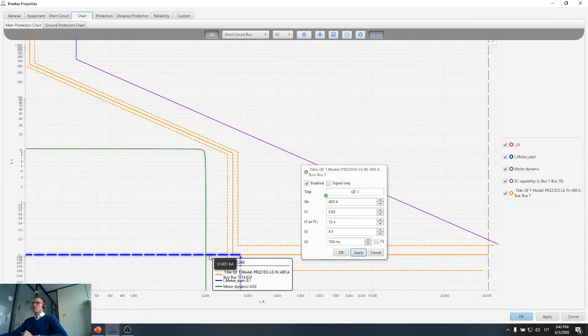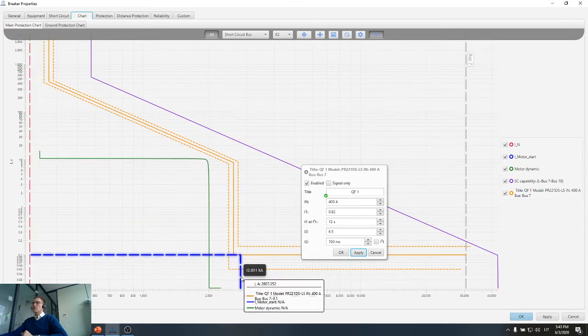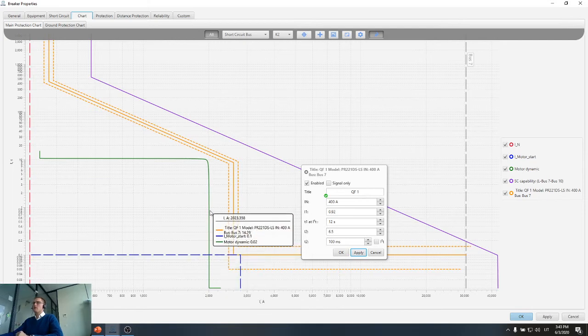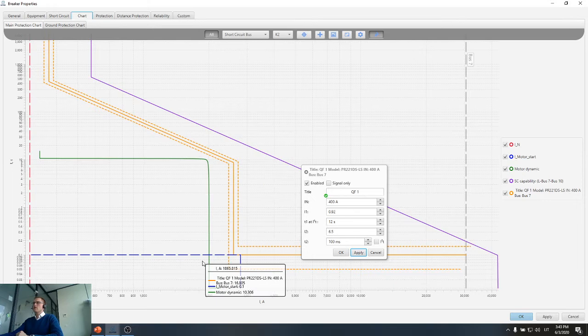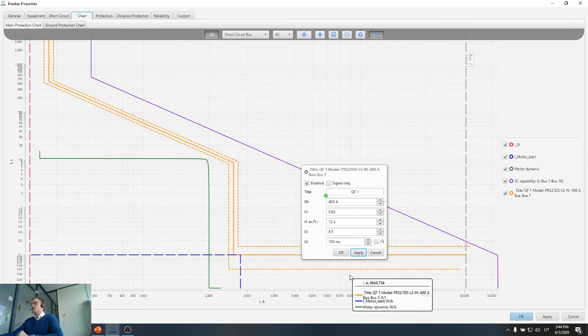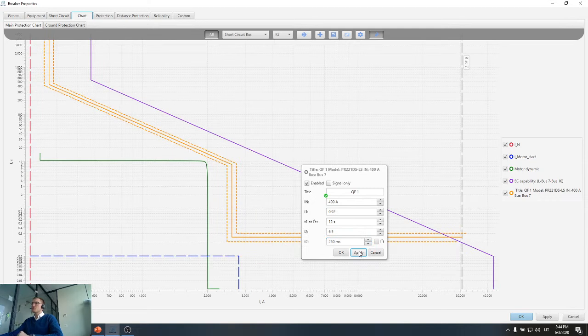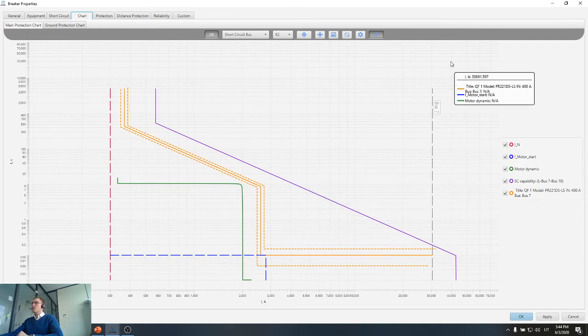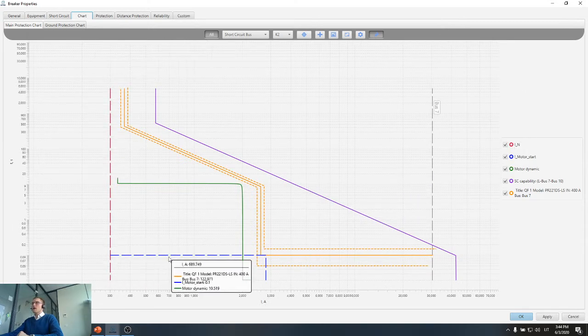Because I see that the recommended calculated motor starting current by the simple starting method is a little bit bigger, I would like to put some safety margin from the dynamic motor starting current, to avoid any tripping during motor starting. Also I can set the short time stage operation time, and here it's 100 milliseconds, which is basically the minimum that is allowed to set for this protection device. I can only increase it, but increasing this time would not be necessary, so I will leave 100 milliseconds as it was before. And here we go, here we have protection coordinated for our motor.